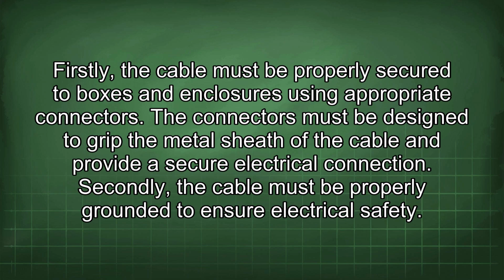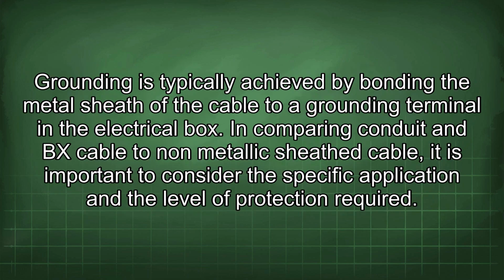Firstly, the cable must be properly secured to boxes and enclosures using appropriate connectors. The connectors must be designed to grip the metal sheath of the cable and provide a secure electrical connection. Secondly, the cable must be properly grounded to ensure electrical safety. Grounding is typically achieved by bonding the metal sheath of the cable to a grounding terminal in the electrical box.